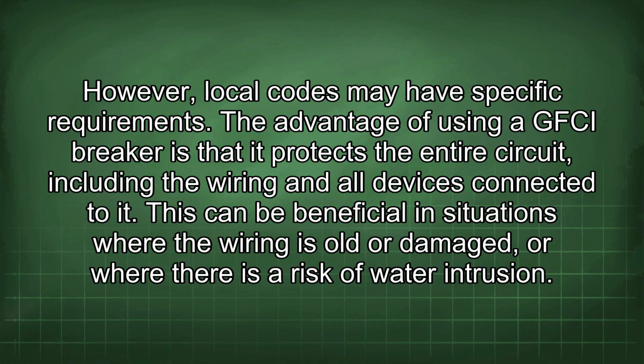The advantage of using a GFCI breaker is that it protects the entire circuit, including the wiring and all devices connected to it. This can be beneficial in situations where the wiring is old or damaged, or where there is a risk of water intrusion.